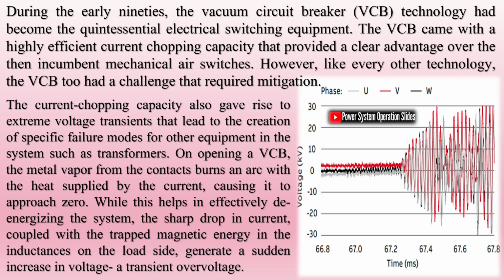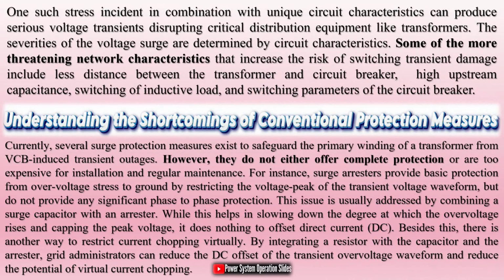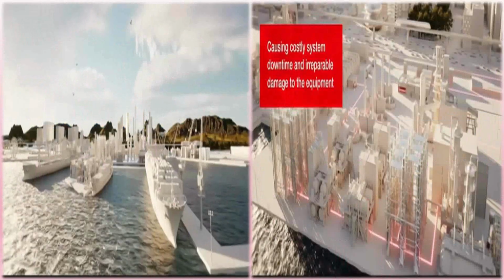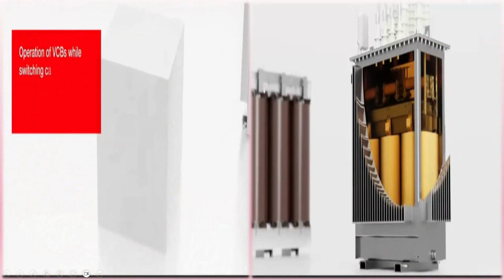On opening a VCB, the metal vapor from the contacts burns an arc with the heat supplied by the current, causing it to approach zero. While this helps in effectively de-energizing the system, the sharp drop in current, coupled with the trapped magnetic energy in the inductances on the load side, generates a sudden increase in voltage, a transient overvoltage. One such stress incident in combination with unique circuit characteristics can produce serious voltage transients disrupting critical distribution equipment like transformers. The severity of the voltage surge is determined by circuit characteristics.